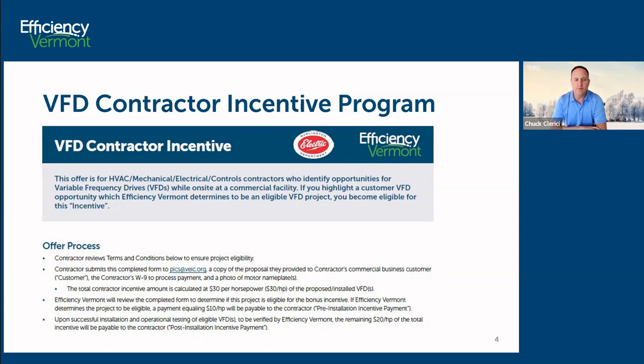So if we don't make sure that these VFDs are modulating and turning down below 60 hertz, the program requirement looks for an average of 54 hertz modulating. If you don't do that, we're actually doing the customer a disservice. We're adding energy to their base load, and that's not the point of the program. So the functional testing piece is very important. We're working on that form right now. There's a meeting Monday, and we expect to have a functional testing form available in the next few weeks.